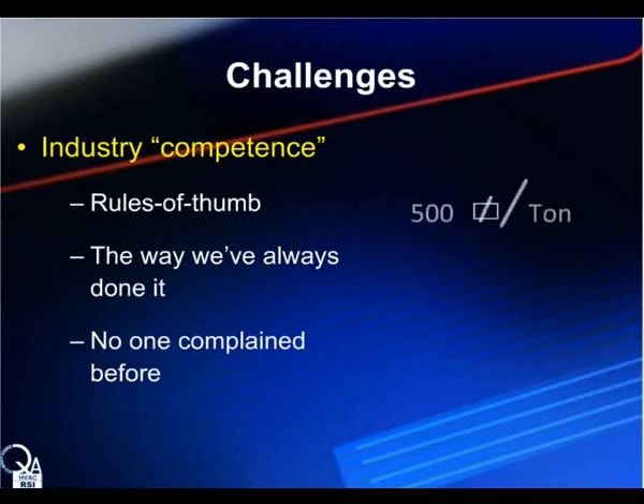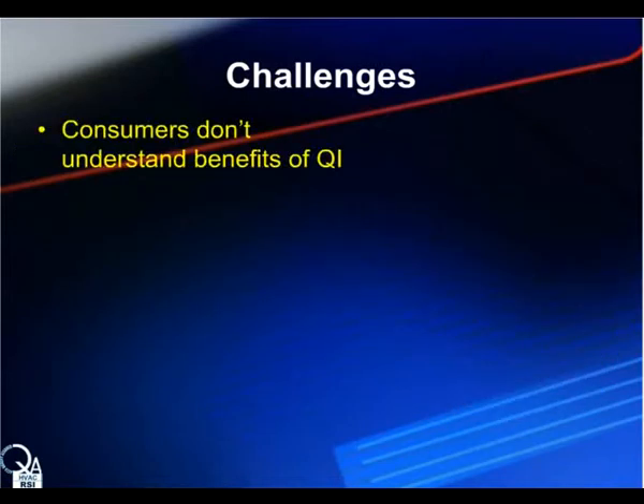Back in the 50s, 500 square foot per ton might have been a good number to eyeball a proposal until the load could be calculated. A cold suction line might have served as an indicator that the system had enough refrigerant to move on to other elements of the installation while the system reached a steady state and the charge could be further refined. And there are others. But as an industry, we must once again do the engineering necessary to properly install an HVAC system. There are other challenges.